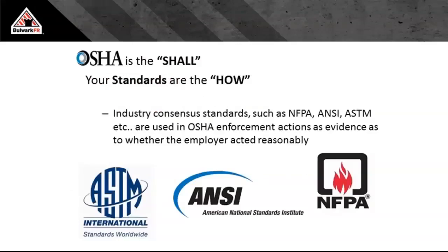So again, in summary, OSHA says you shall protect your people. There is more than enough regulations out there when it comes to PPE to tell us to do that. But where's the how? You shall protect me, but where's my how? My how comes from my standards. As we said earlier, whether that's the ANSI standards, ASTM standards, and NFPA standards, and within the FR and arc-rated world, flame-resistant and arc-rated world, we use these standards in combinations. ASTM gives us a lot of test methodology. And in fact, we'll talk about one of the ASTM tests today that helps us get an arc rating in order to tell you in NFPA what to wear.